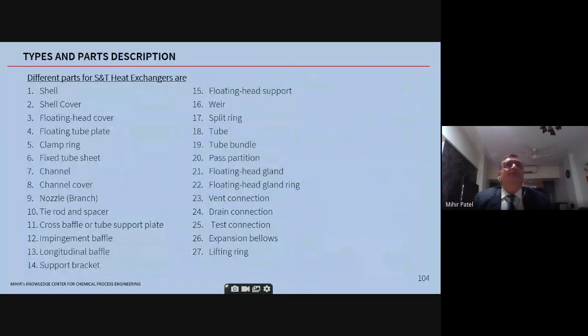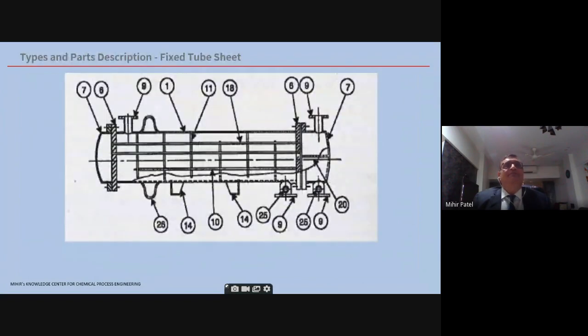So, different parts of a shell and tube exchanger, just for information. Many parts are there. There is a fixed tube sheet type as shown here. On the left, you see an expansion bellow on the shell side. Okay, this is used for thermal expansion. One has to be careful with the expansion bellow. I have seen a consultancy specify an expansion bellow for a large temperature differential heat exchanger, and the expansion bellow failed. Luckily, no fatalities were caused. So if you have a very large temperature gradient across the exchanger, then you should not specify an expansion bellow. It is better to go with the S type or T type or the U type.